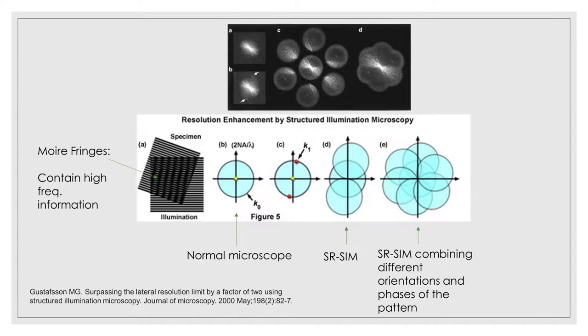The reconstruction algorithm is in Fourier space, and it uses something called the optical transfer function, the OTF. The OTF is the Fourier transform of the point spread function, which was shown earlier. To get the best reconstruction, the OTF of the measured sample must be the same as that used in the algorithm. Otherwise, there'll be reconstruction artefacts. And for this reason, the point spread function is measured experimentally using fluorescent beads first. And this is then used to create OTFs, which are used in the reconstruction.